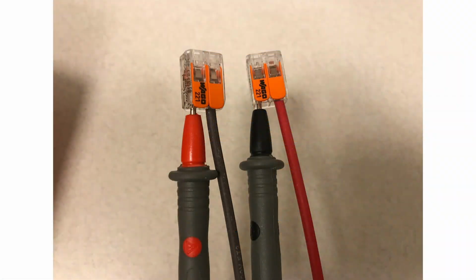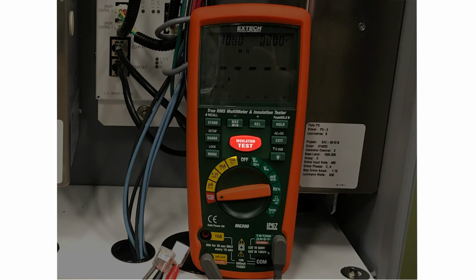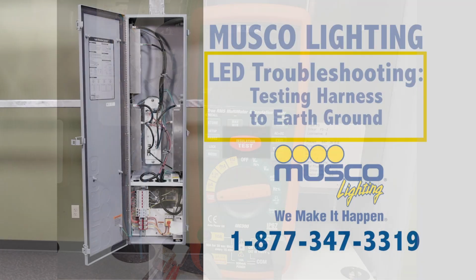Hook your meter up red to black and black to red, then press the insulation test button and hold for 45 seconds, recording both resistance and voltage, if your meter gives you a voltage reading. Testing will not cause a good fixture to glow. If the fixture does glow, this indicates a reverse in polarity.